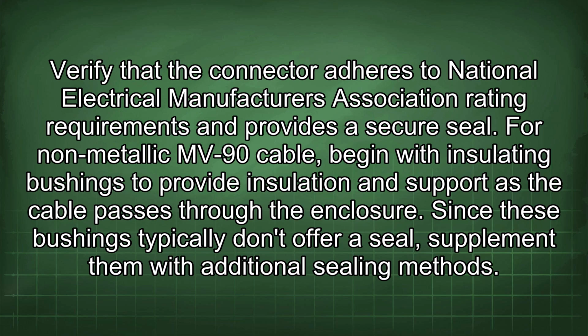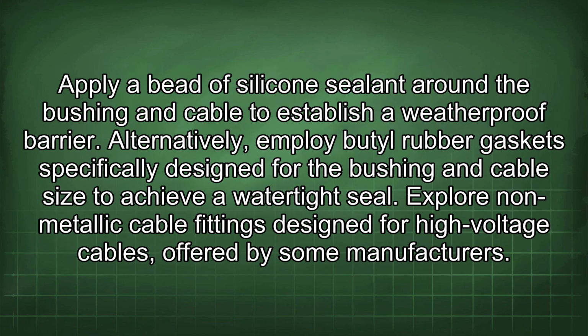For non-metallic MV-90 cable, begin with insulating bushings to provide insulation and support as the cable passes through the enclosure. Since these bushings typically don't offer a seal, supplement them with additional sealing methods. Apply a bead of silicone sealant around the bushing and cable to establish a weatherproof barrier. Alternatively, employ butyl rubber gaskets specifically designed for the bushing and cable size to achieve a watertight seal.